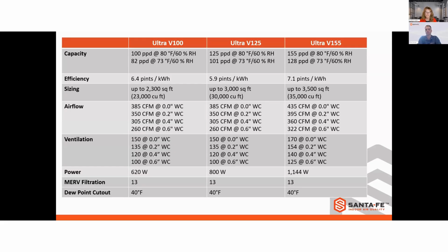And what's really amazing is these are the first dehumidifiers on the market that we are actually giving you the ventilation rates at the different static pressures. So you have a better idea of what to expect when you are going in and wanting to provide ventilation for these homes, what you're going to be able to get out of these units at those different statics. All of them include MERV 13 filtration. That is standard on all of our units. And we have incorporated a dew point cutout of 40 degrees on our new units as well.